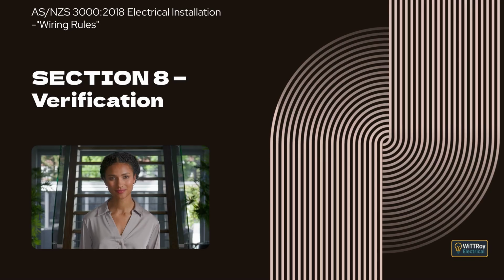The notes explain that when supply is available, earth fault loop impedance testing is preferred because it verifies the complete earth fault loop, including the integrity of the MEN connection and the supply neutral or PEN conductors. Where supply is not available, the resistance method establishes the contribution of the final subcircuit to the total earth fault loop impedance.